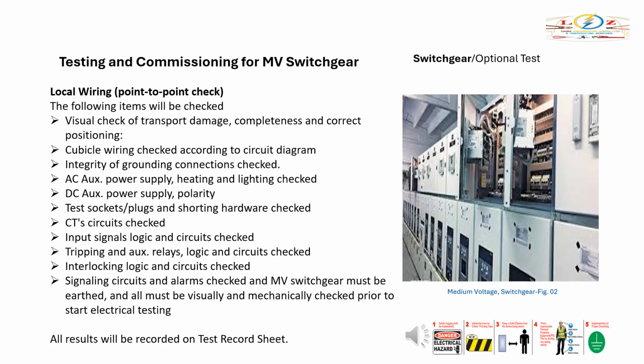Local wiring, point-to-point check. The following items will be checked. Visual check of transport damage, completeness and correct positioning. Cubicle wiring checked according to circuit diagram. Integrity of grounding connections checked. AC auxiliary power supply, heating and lighting checked. DC auxiliary power supply, polarity. Test sockets, plugs and shorting hardware checked.